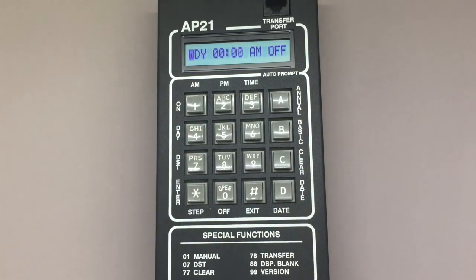In this example, I'm going to program for school zone flashers, which I don't want to turn on over the weekend. So I'm going to scroll back to WDY, which represents weekdays.